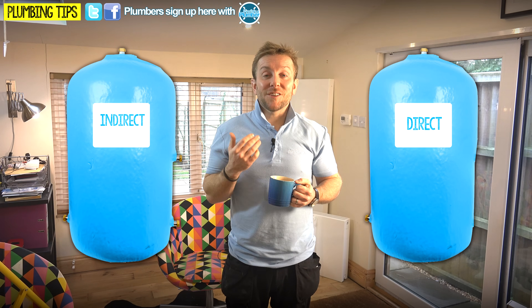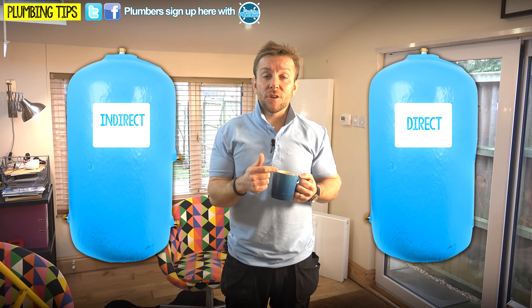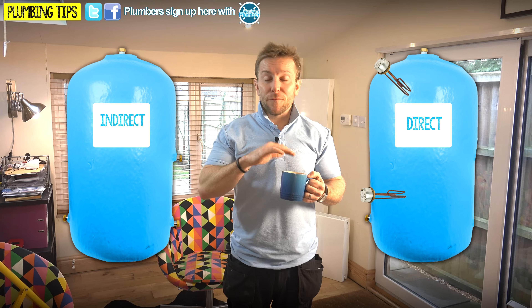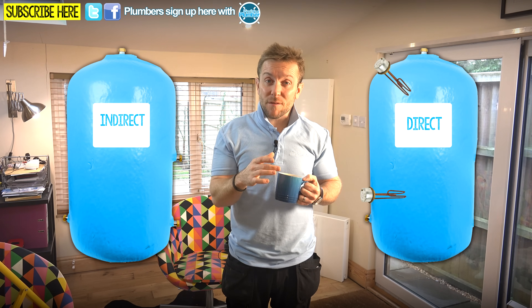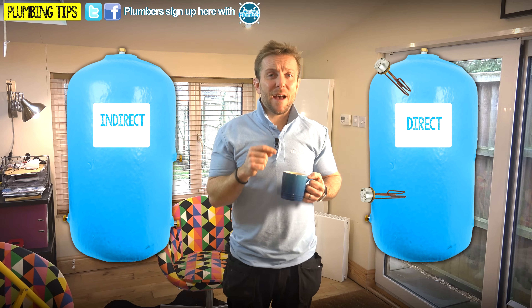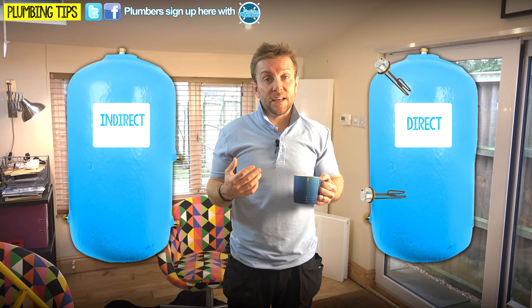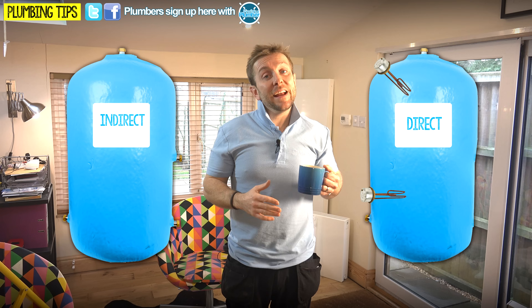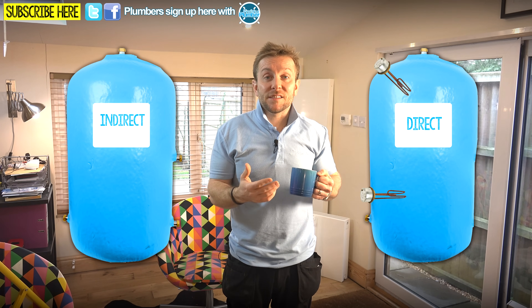If we look at the direct tank on this side, it's so much more simple. There is no coil - you don't have a coil coming from the boiler. All you have is usually an immersion heater at the bottom and sometimes one at the top as well. This is especially common on Economy 7 and Economy 10 systems - the difference between the 7 and the 10 being purely how much cheap-rate electricity you have. The top immersion heater is a boost immersion heater, so if you get back at 10 o'clock on a Saturday morning at a high rate of electricity but still want a bath, you press that boost and it heats the top part of the cylinder up. Then at night when you've got a lower rate of electricity, the bottom one - the night setback immersion - comes on and heats the whole tank up. That makes it a direct cylinder.